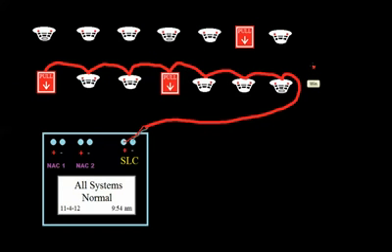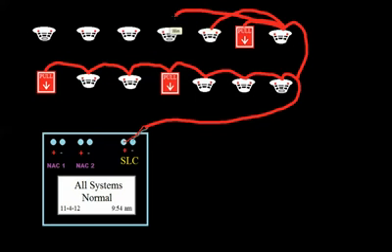Well, here I can do something called T-tapping. Depending on the style of wiring, there's certain systems where this is not allowed. We'll get into that in the future. Let's say I had a connection here. I'd have like some wire nuts and stuff like that. I can just tap off right here. I could tap off any way I want. I mean, this is kind of confusing, but just to make my point, I don't have to go in any specific order. All I need is all of these devices to be somehow connected back to that panel, and I'll explain why.